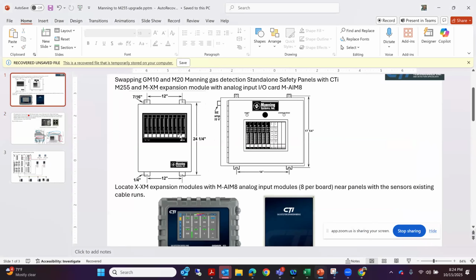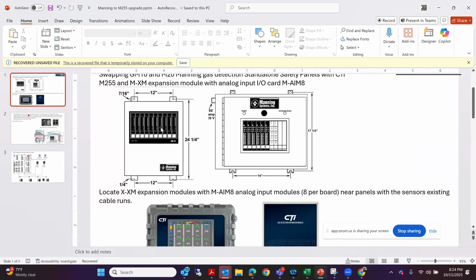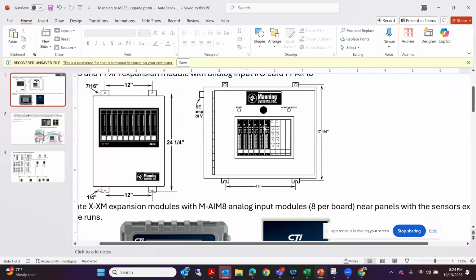Some of the old GM10 manning panels were really common, and a lot of people are still using them. Even the old M20s at least had a calibration mode, but this old standalone manning panel system here had no cal mode. There was no turning off those shunt or output functions to keep you from tripping your output audio visual or accidentally shunt tripping the compressor room when you were trying to maintain your sensors.